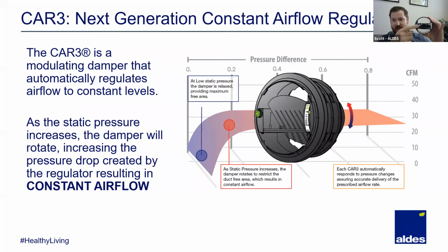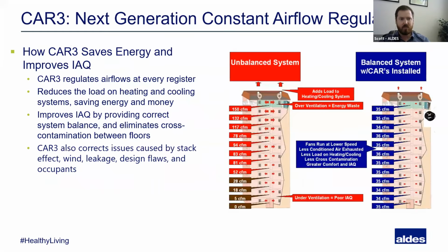So with very little pressure, it's going to be more on the bottom, more relaxed, and with more pressure, it's going to be more closed. And it's going to automatically adjust itself to whatever position is necessary in order to maintain flow. So as I have things like filters loading, fans changing speed, stack effect, that device is going to automatically adjust to maintain constant airflow. So it's a constant airflow regulator. So how is that going to save us energy and IAQ?